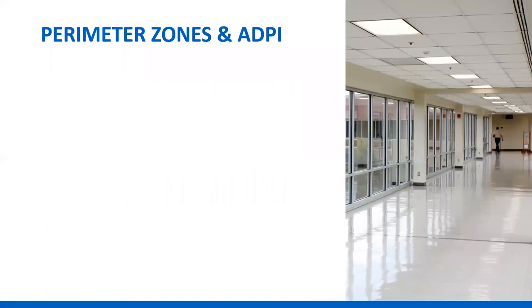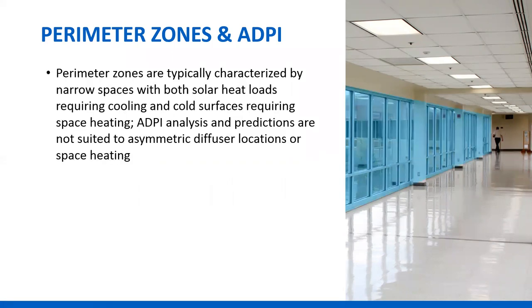Because of the asymmetrical nature of air distribution — you need to have it closer to the window, not the center of the space — it causes a problem trying to do ADPI in a perimeter zone. ADPI assumes uniform air distribution in all directions from a diffuser, so it's difficult to make ADPI work in an asymmetric diffuser location. While there is some interesting data coming on doing ADPI for heating, the details haven't been worked out yet — so for now, you're not going to use ADPI in a perimeter zone.